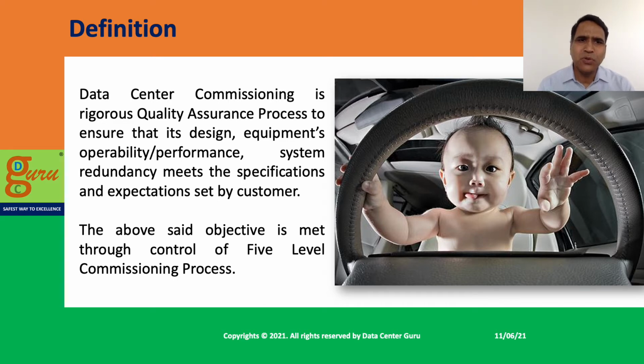These activities or outcomes can be done through a control process called the 5 level commissioning process. Commissioning is a process and part of quality control or quality management system, and commissioning is a control point. What commissioning does is check and control at multiple stages of the project to ensure specific requirements are met, so it is not done only at the end of the project, but at every stage, so that if there are shortcomings or gaps, you are able to identify and rectify them at the right time instead of identifying those things at the end of the project.